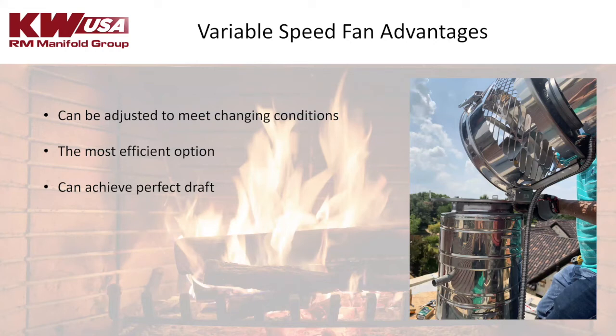It's a little picture of it, and it also uses a variable speed motor, which is really important when you are installing a mechanical draft system, to always use one with a variable speed motor, because they can be adjusted to meet the changing conditions of the draft. As that fire heats up and gets going and starts drafting properly, you can turn the fan down so it's not overdrafting. So variable speed fans are the most efficient option for a mechanical draft system, and if used properly, they can achieve the holy grail of perfect draft.